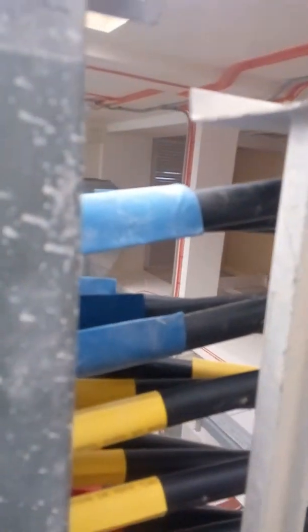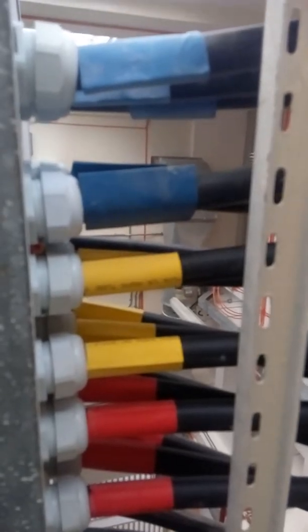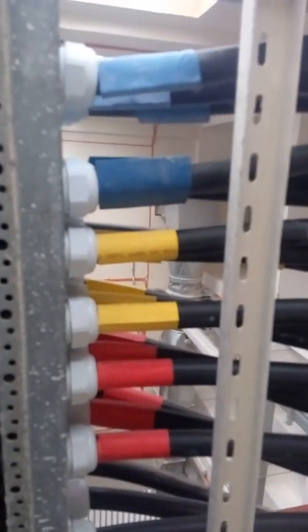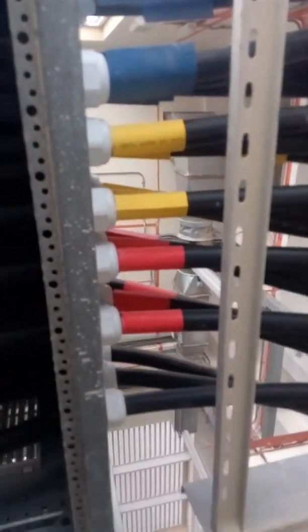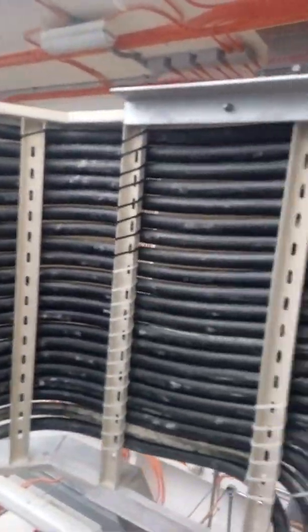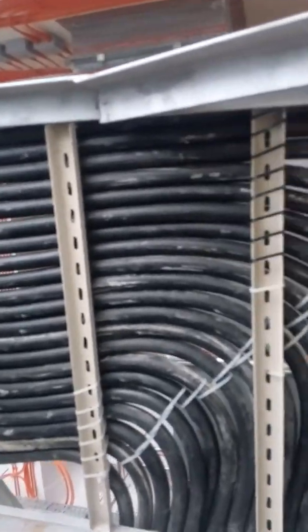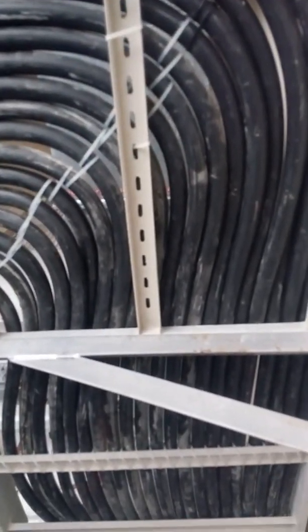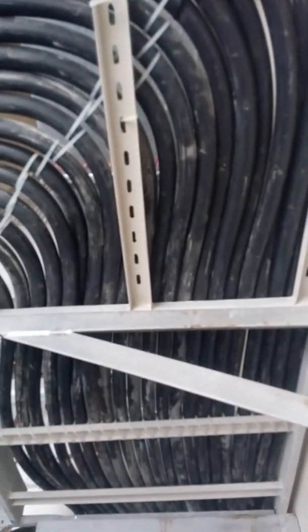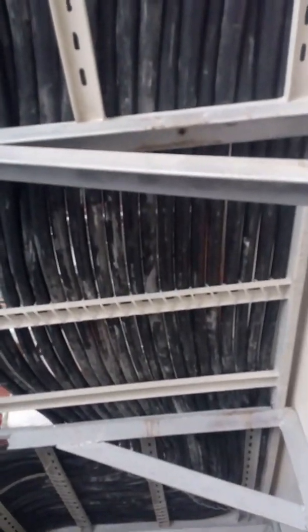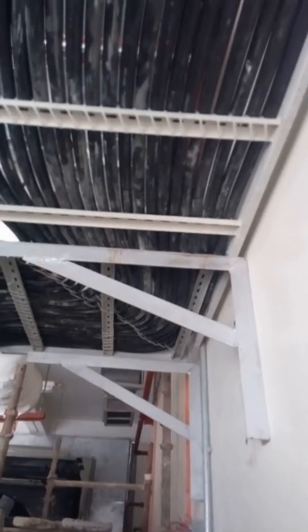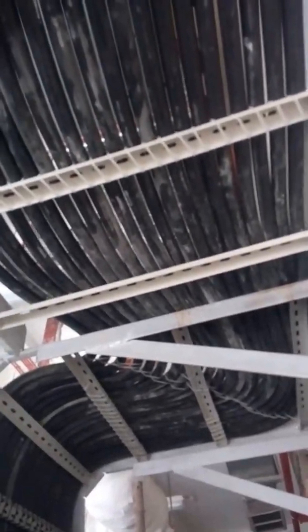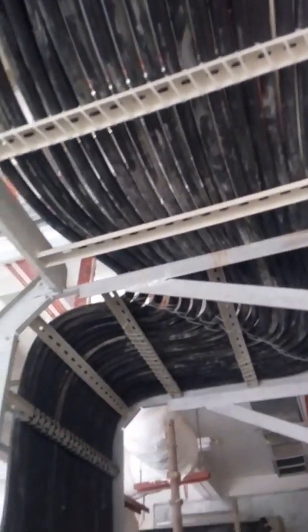So this is the busbar, you see busbar already have different different terminals. So from here, this is the cable already from this area, already put the PVC gland. And also identified by identification of the color, we have blue, we have yellow, and red. So coming here, here already dressed properly.